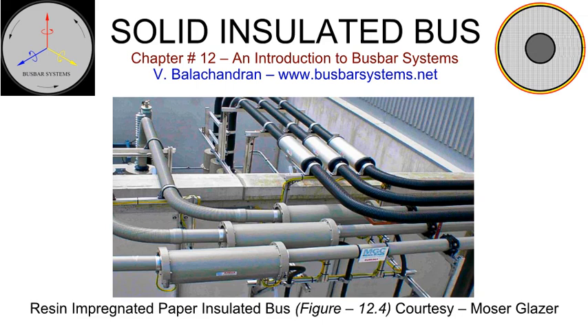The insulated conductors are made as long as is permitted by constraints of transport and installation. Bends are an integral part of the insulated conductor. The maximum length of the single conductor depends upon the rigidity of the conductor. The larger the diameter of the conductor, the longer can be the individual length of the conductor. Conductors can be manufactured with a straight length of up to 13 meters, 43 feet 4 inches, with 1 or 2 right-angle bends totaling 3 meters, 10 feet.